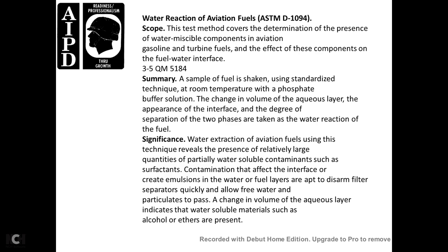Significance: water extraction technique reveals the presence of relatively large quantities of potential water-soluble contamination such as surfactants that affect the interface, creating emulsions in the water-fuel layers which may disrupt filter separation. Changes in the volume of the aqueous layer indicate water-soluble materials such as alcohols and ethers are present.